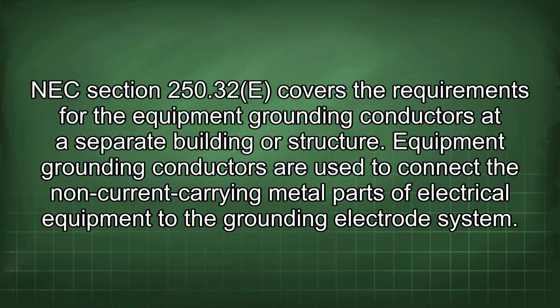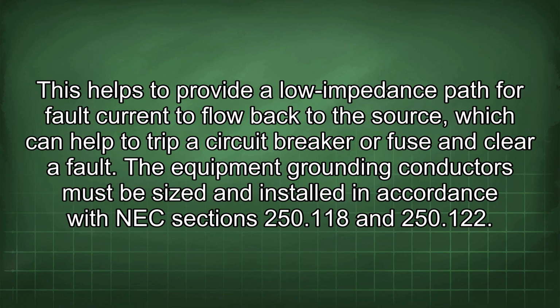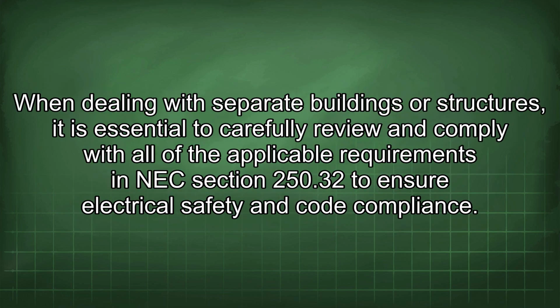NEC Section 250.32e covers the requirements for the equipment grounding conductors at a separate building or structure. Equipment grounding conductors are used to connect the non-current carrying metal parts of electrical equipment to the grounding electrode system. This helps to provide a low impedance path for fault current to flow back to the source, which can help to trip a circuit breaker or fuse and clear a fault. The equipment grounding conductors must be sized and installed in accordance with NEC sections 250.118 and 250.122. When dealing with separate buildings or structures, it is essential to carefully review and comply with all of the applicable requirements in NEC section 250.32 to ensure electrical safety and code compliance.